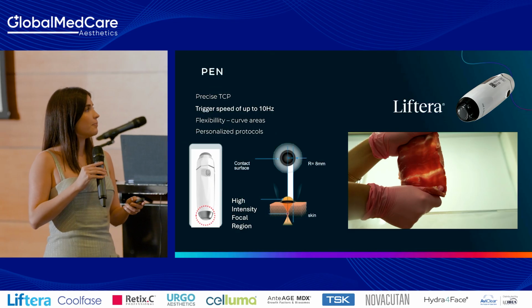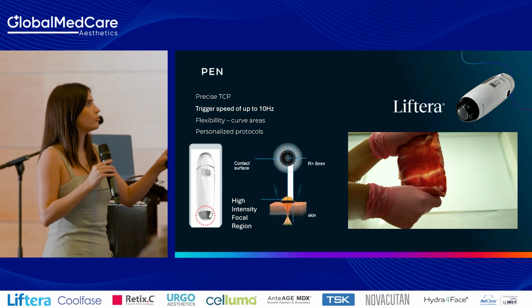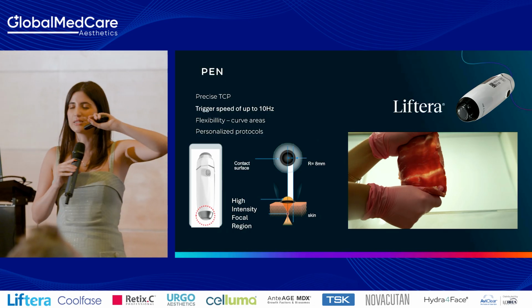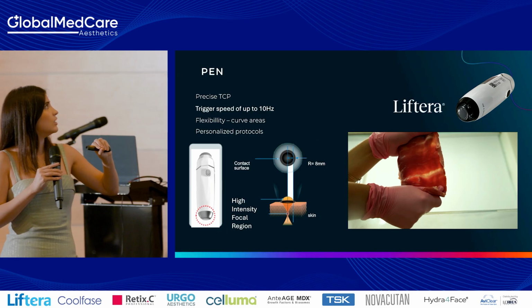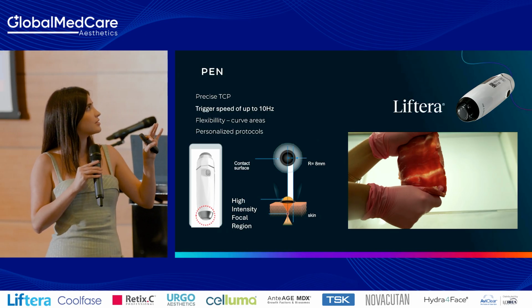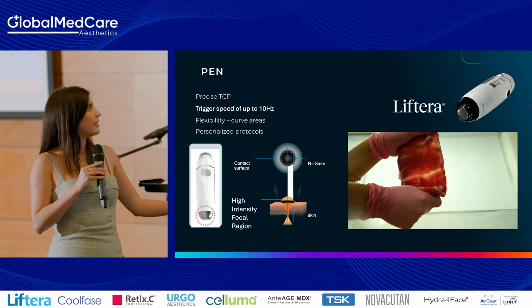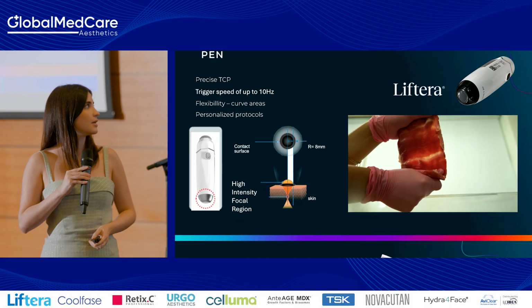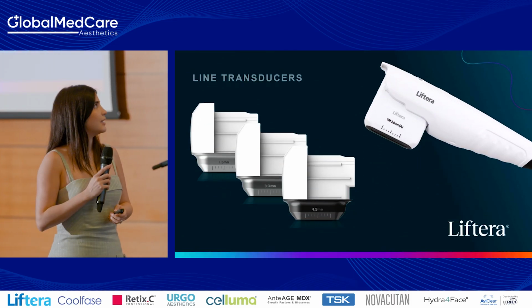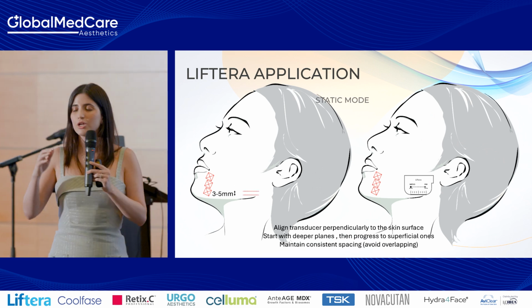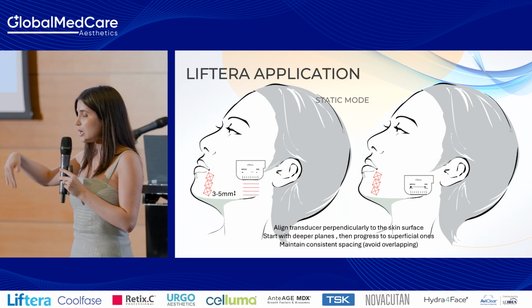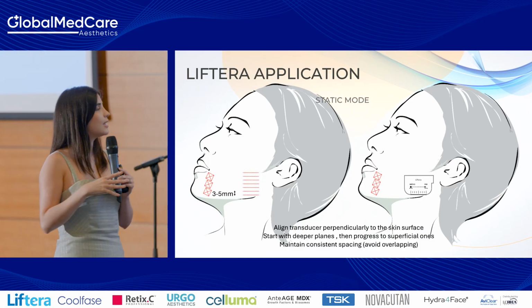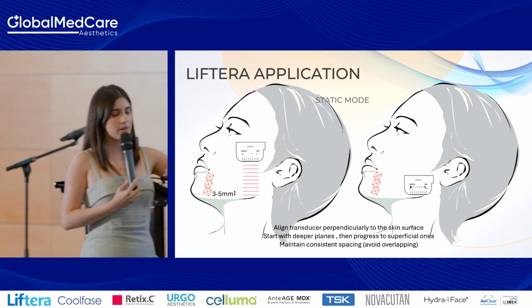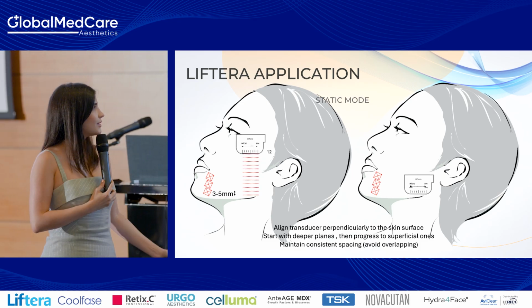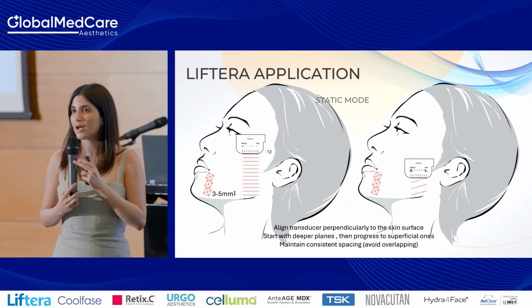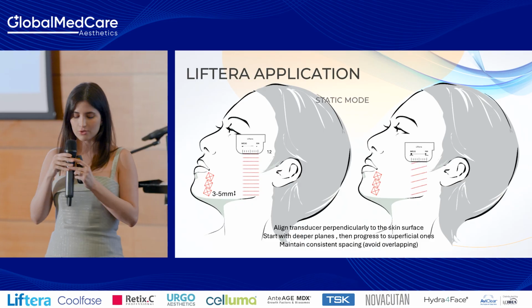And here is how the pen works. I don't know if the light will allow you to see, but there are small dots. The pen is very precise, and you have this flexibility to treat curved areas with more precise TCPs. It's only delivered here in the center of our contact surface. With the line applicators it's a little bit different, because here you have to work in a static mode, not moving as with the pen. You need to align your transducer as perpendicular as possible to the surface and try to maintain this spacing, avoiding overlapping. What I recommend to you is 3 to 5 millimeters.